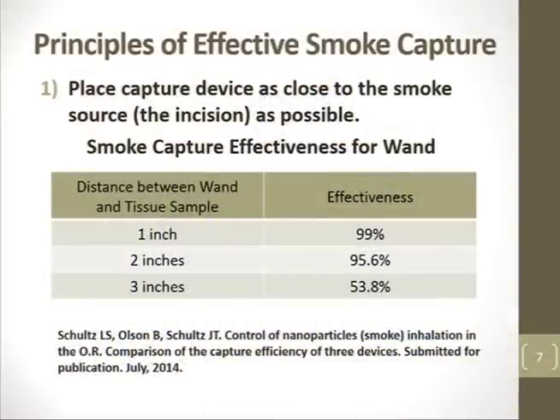This slide points out that in order to capture smoke effectively, the orifice of the capture device, whether it's a tube or any other device, has to be as close to the source of smoke production as possible. A number of studies done at the University of Minnesota, Department of Mechanical Engineering Particle Calibration Laboratory, where these results were obtained, indicate that if you were to keep an open tube, which we call a wand, close to the source of smoke production, as little as 1 inch or 2 inches, the smoke capture efficiency is very high. If you move it back to 3 inches, however, from the source of smoke, the efficiency drops down by half.